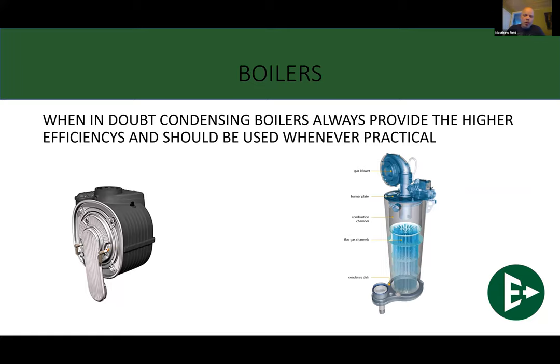tube heat exchanger, where we have really, really low head loss, but it is a bit more complex to take apart and clean. This was actually sold when it first hit the marketplace as a self-cleaning heat exchanger. That is absolutely not true at all. You still need to take it apart. You still need to clean it.